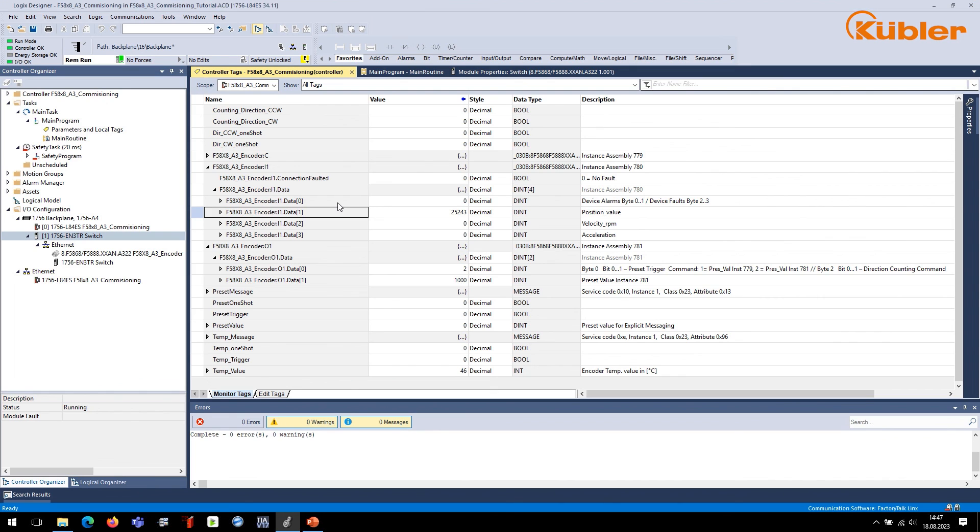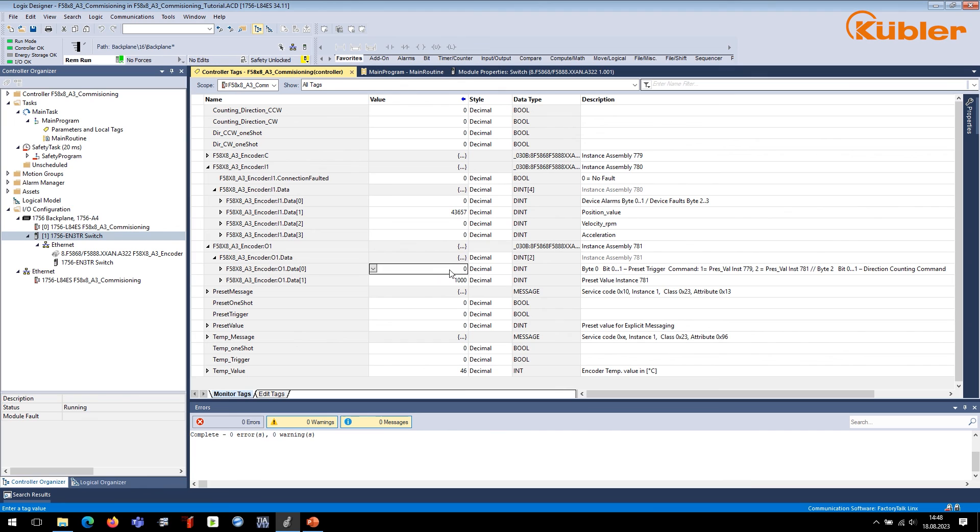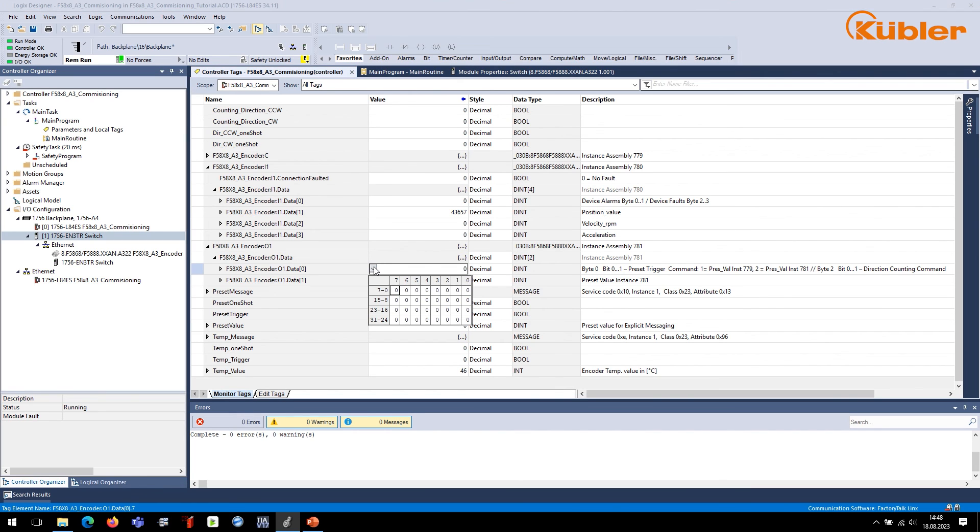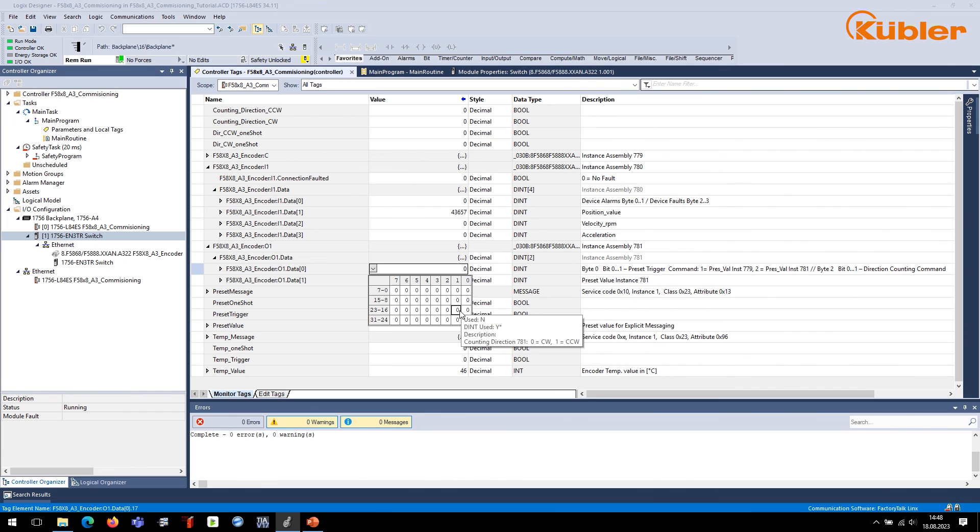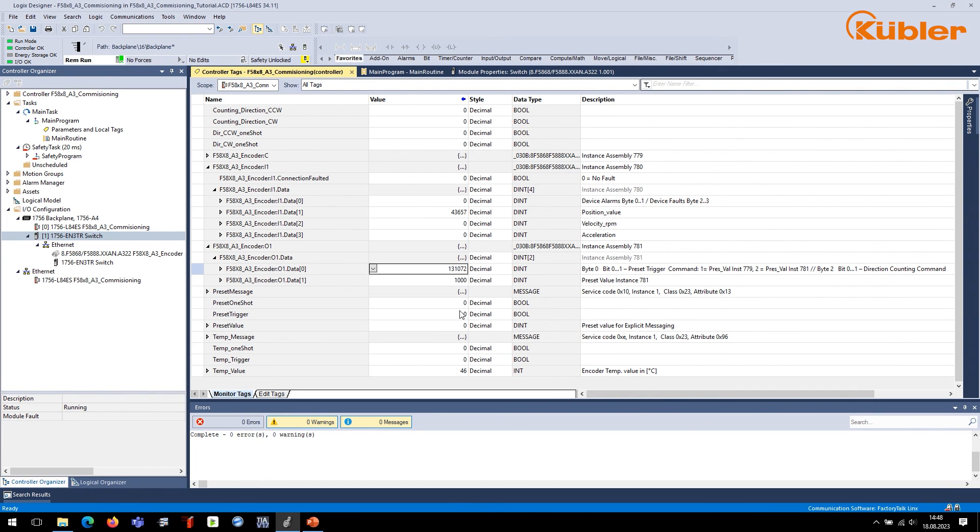To reverse the counting direction, set the direction counting trigger bits in byte 2 of output assembly number 781 to 0. Then, let the PLC establish the connection to the encoder. Now, set the direction counting trigger bits to 2. By turning the shaft of the encoder counterclockwise, the position value will now rise.